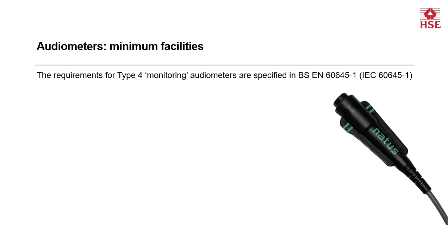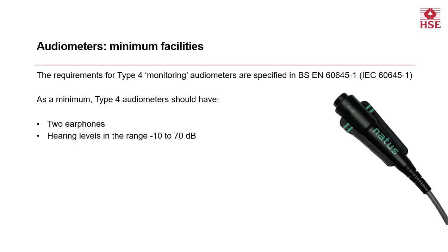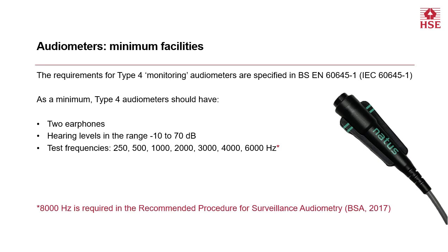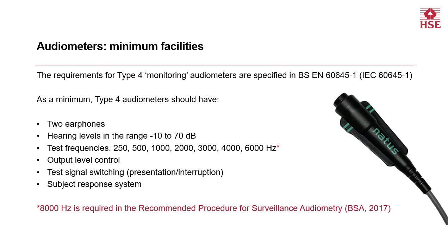For surveillance audiometry, an audiometer meeting the Type 4 specification in BSEN 60645-1 should suffice with one caveat. In this standard, a Type 4 audiometer is required to have two earphones, hearing levels in the range -10 to 70 dB, test frequencies from 250 Hz up to 6 kHz, and here is the caveat, 8 kHz is required in the BSA recommended procedure for surveillance audiometry and in HSE's L108 guidance document. It should also have output level control, test signal switching, and a subject response system. In other words, be mindful that it's possible for an audiometer to meet the Type 4 specification but not include all the test frequencies that you need.